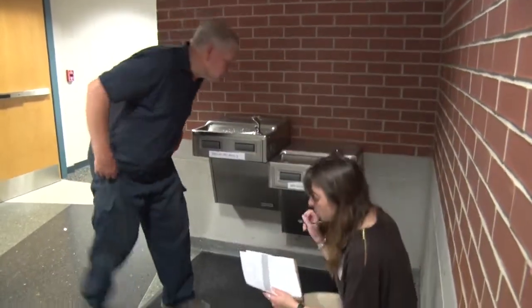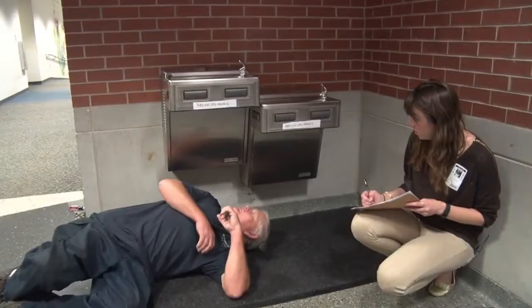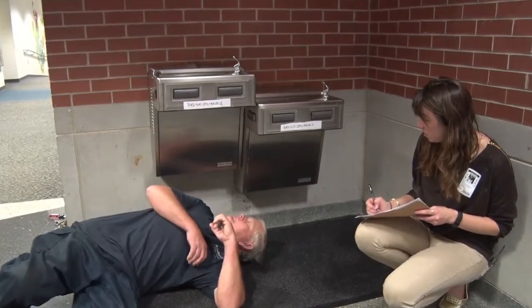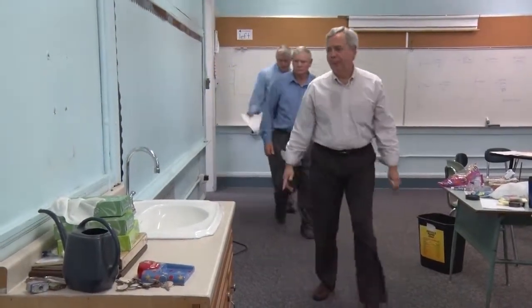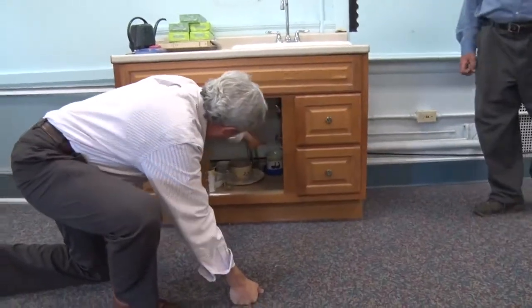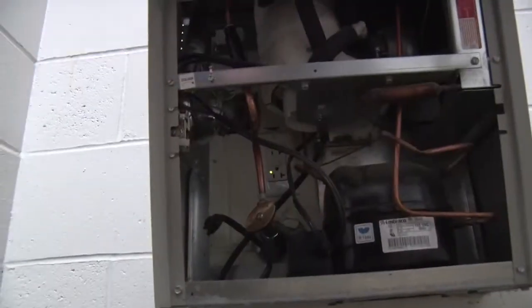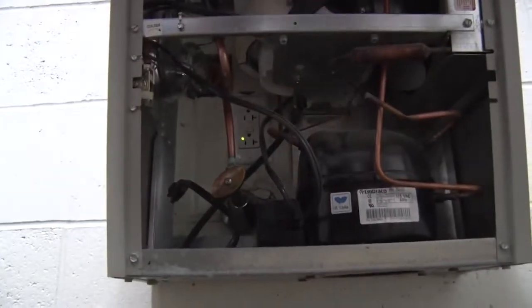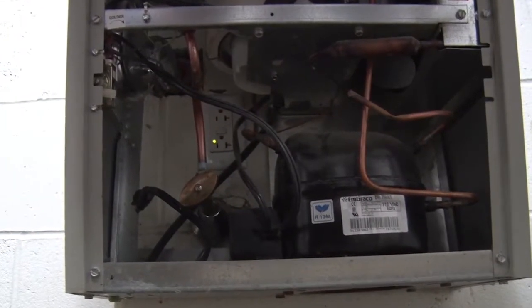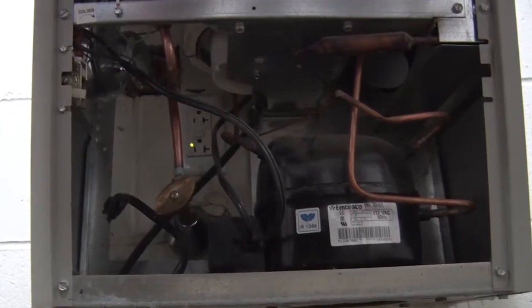The make and model of all water coolers should be documented on the drinking water outlet inventory and compared to EPA's recall list. Document if any drinking water outlet has a filter and provide information regarding the filter installed on the filter inventory, including the make and model of the filter, the date the filter was installed, the replacement frequency of the filter, and if the filter removes lead.